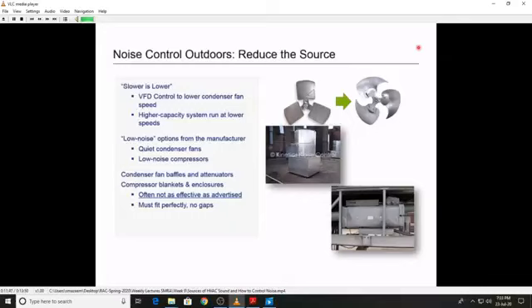You can put baffles and attenuators over your condenser fans. That's very common on very large fans. It's less common on smaller fans. But here you see a case where there are neighbors looking over the units. And so the noise that normally would never be a problem on a rooftop is suddenly coming right in their windows, and an attenuator is necessary. Or compressor blankets and enclosures. They're very popular as an attack on compressor noise. However, it's very difficult to do it right, and quite often these compressor blankets do not work as advertised, not because of poor advertisement, but because they have to fit absolutely perfectly with no gaps in order to be effective. Because again, sound gets through gaps.